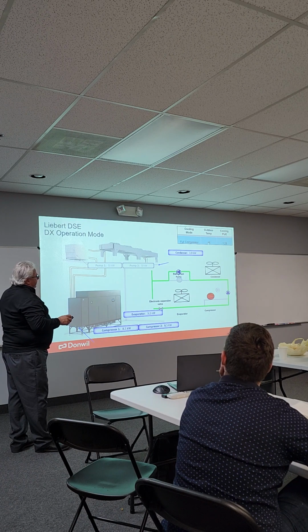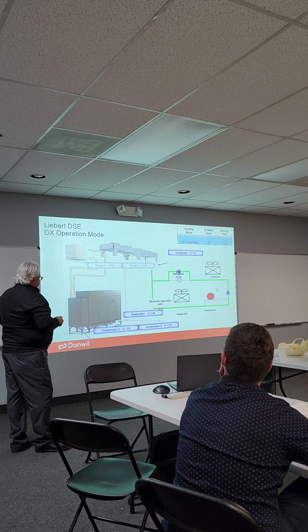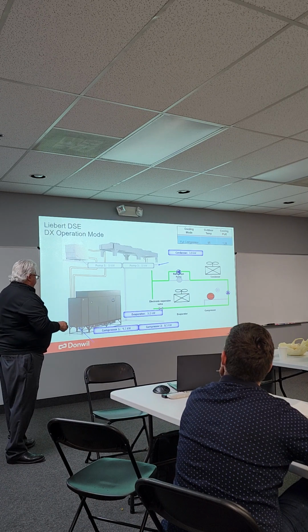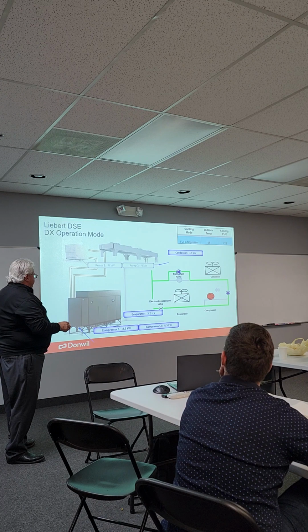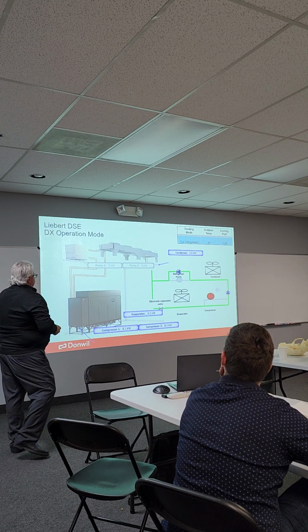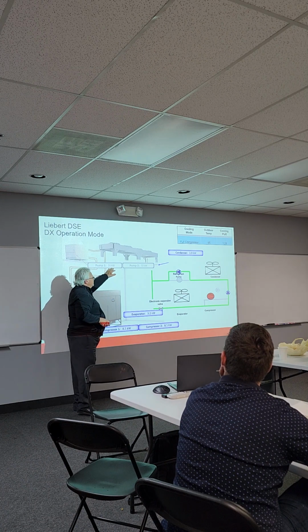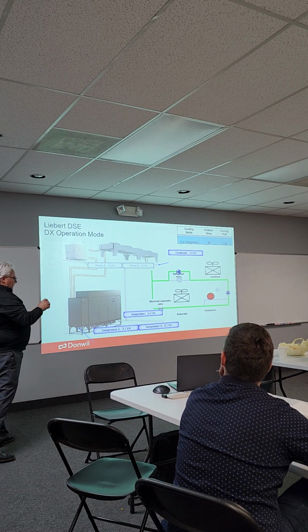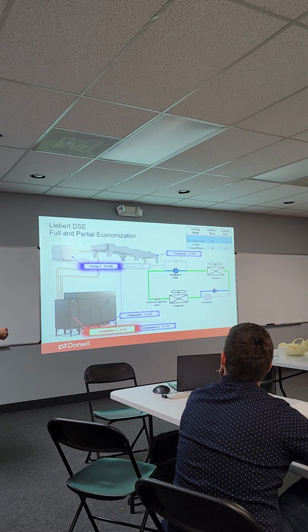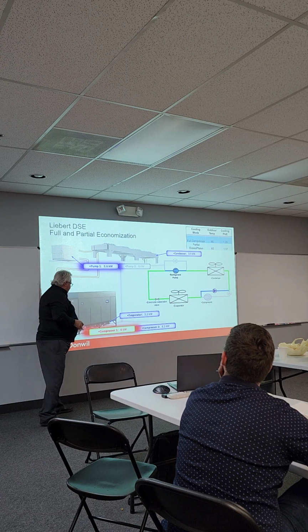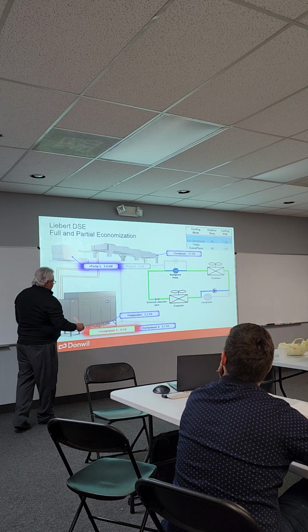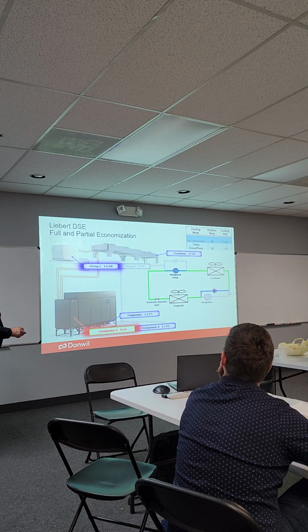So on a 95 degree day, no economization. Both compressors are on, they're drawing 8.5 kW apiece. Evaporator fan is 3.2, and the pumps are doing nothing. Condenser's 3.9. Now, we go to a 65-degree day. We could actually start to shut off compressor 1. Compressor 2 is still working. Evaporator still working. We have a pump on, moving refrigerant in circuit 1. It's only drawing 0.6 kW. Pump 2 is off.